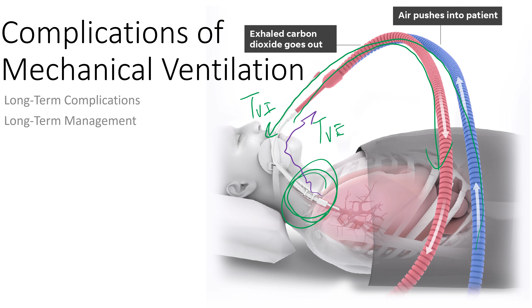So what kind of pressure alarms would I get on the ventilator if that's happening? You get a low pressure alarm, right? And I'm going to see on the ventilator that the volume that is set is not what I'm getting, and they can even tell you those two values. They say, oh, you're getting 400 in, and you're getting 200 back. The other 200 is escaping out the mouth, and they're talking to you, right? They're rattling secretions, they're making noises, which they shouldn't, right?